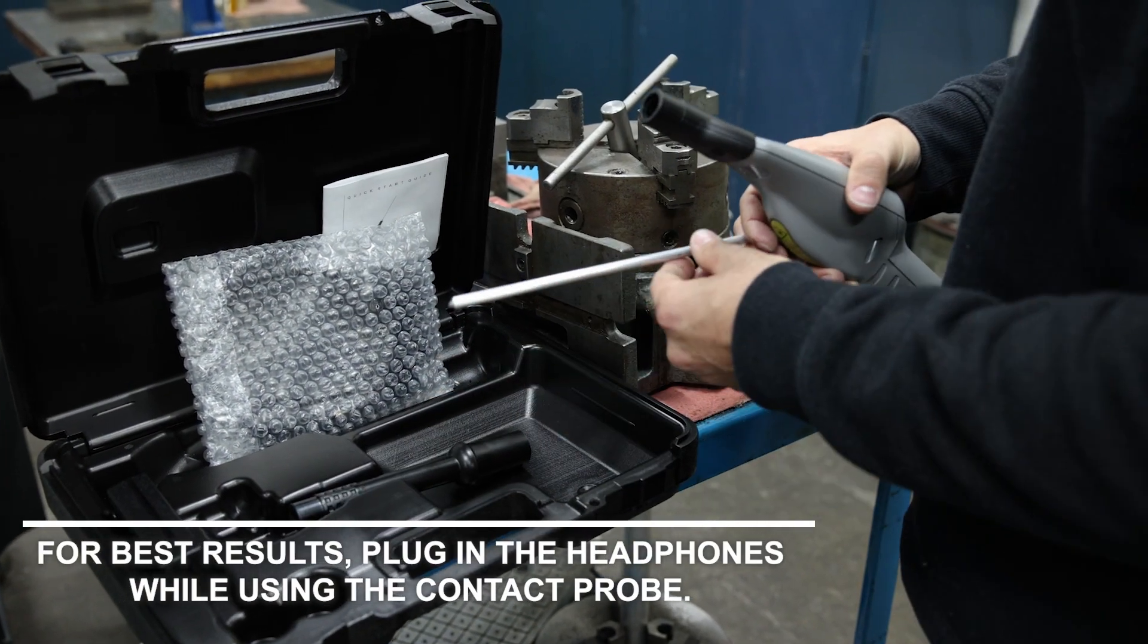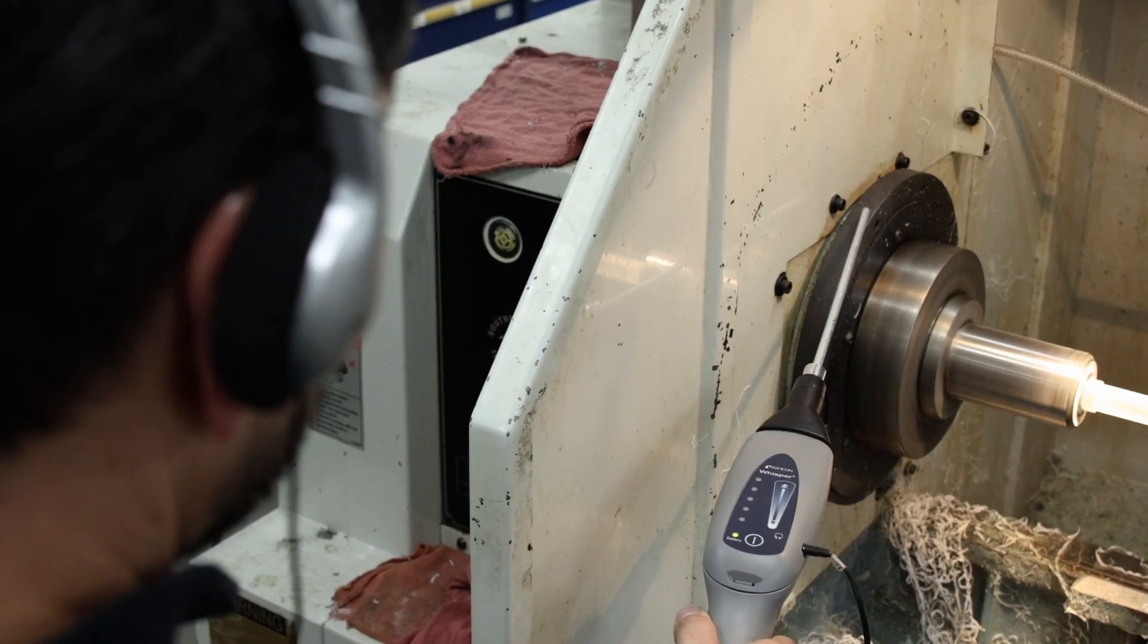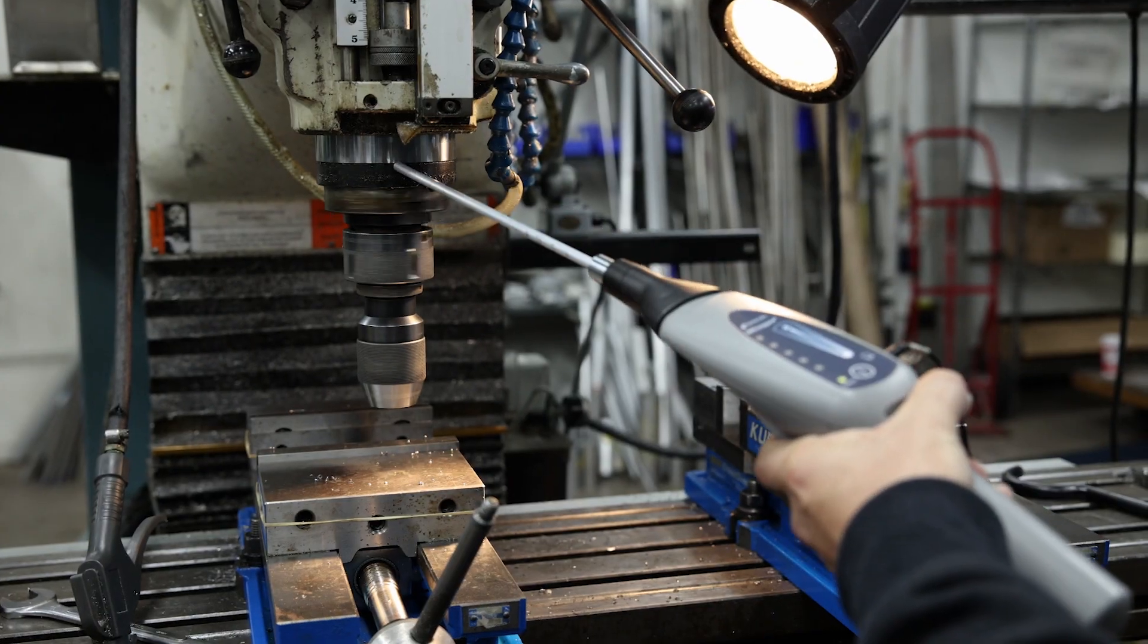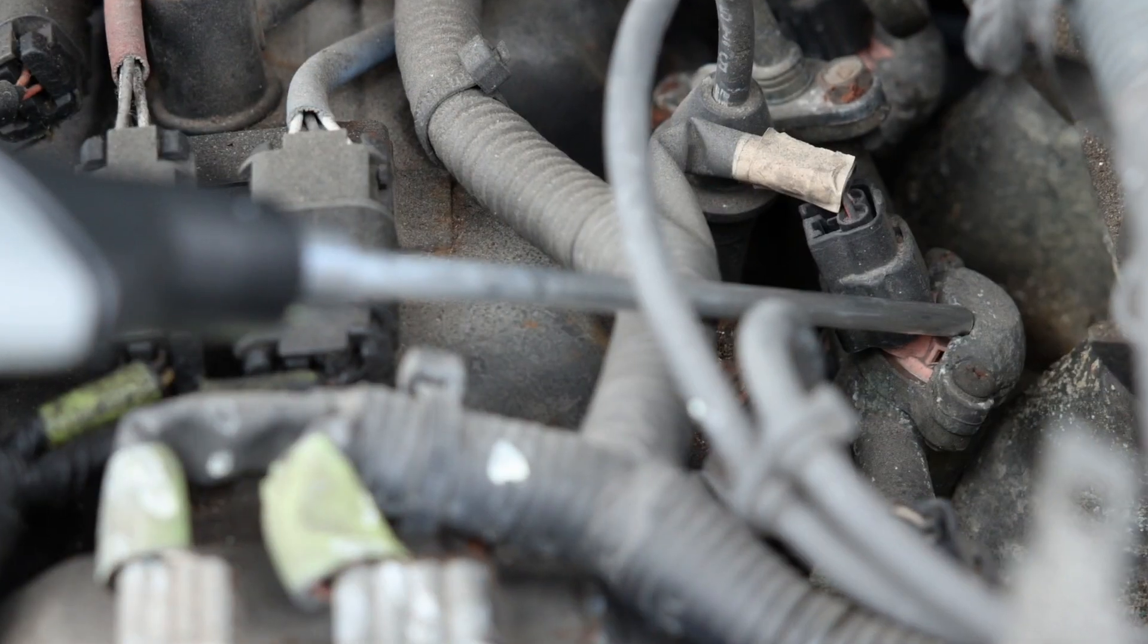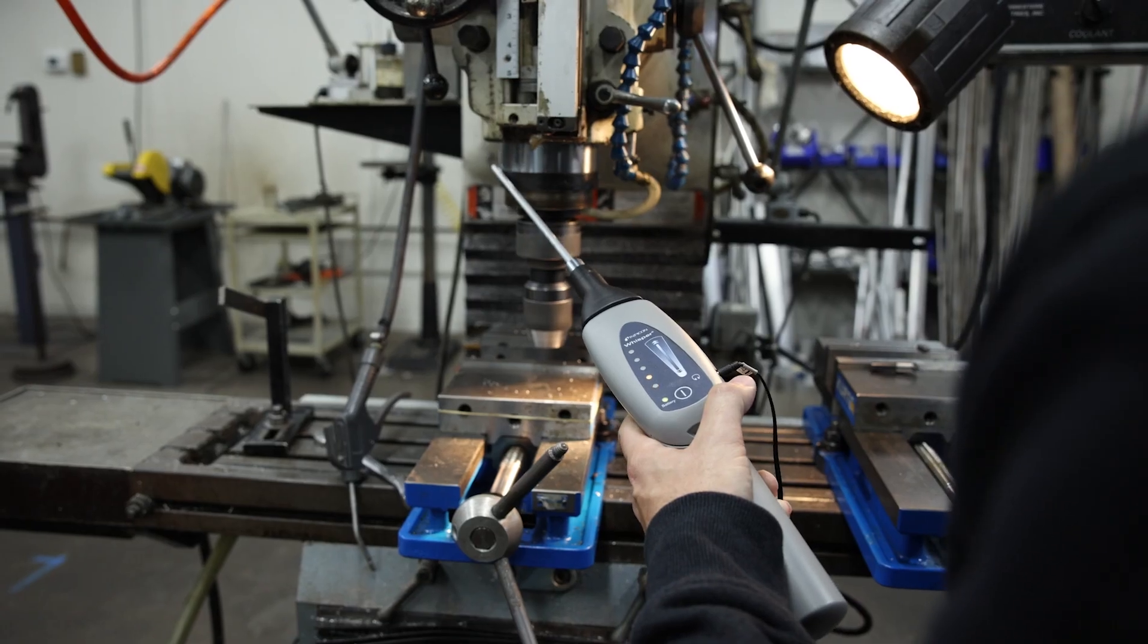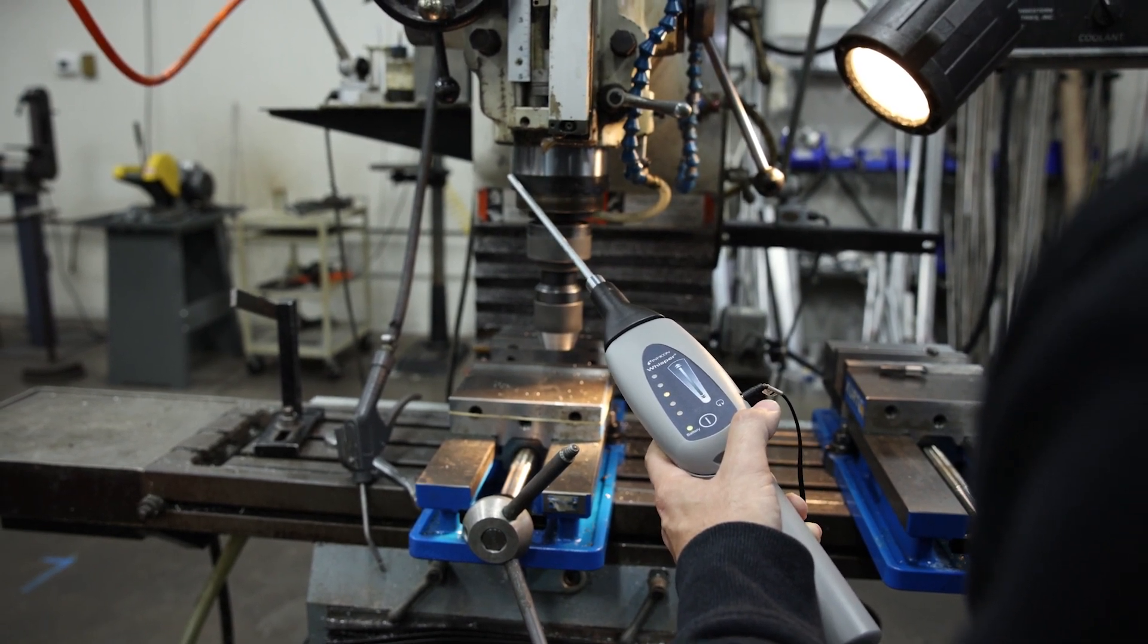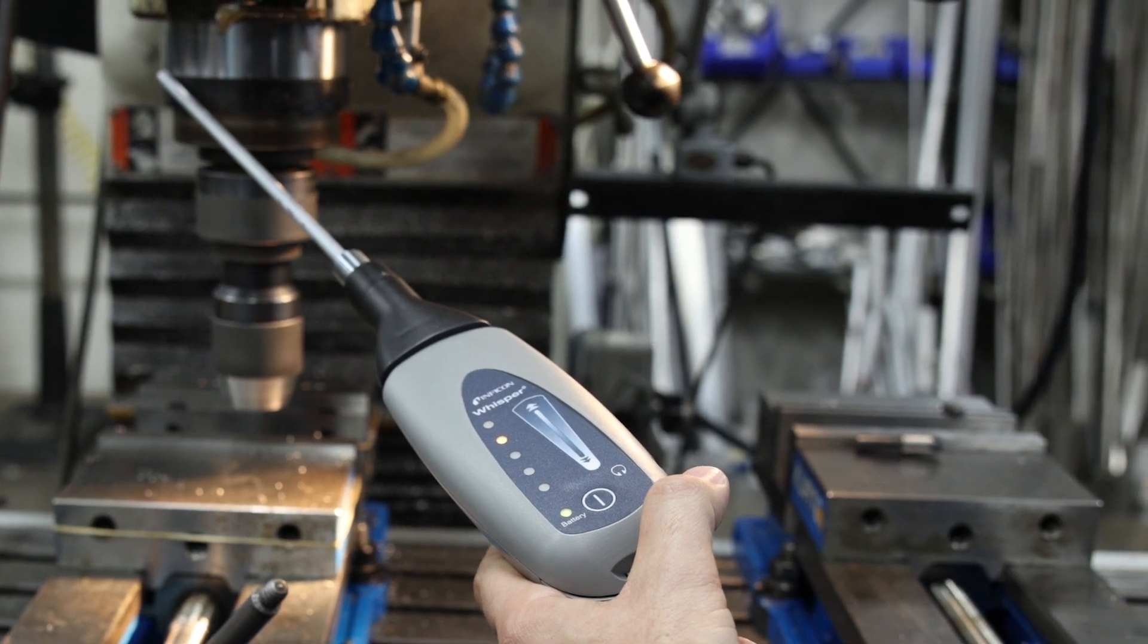Connect the contact probe to pinpoint worn or damaged mechanical components like gears, bearings, solenoids, or pistons. Properly functioning machinery sounds smooth and clear. Poorly functioning machinery may make irregular or grinding noises.